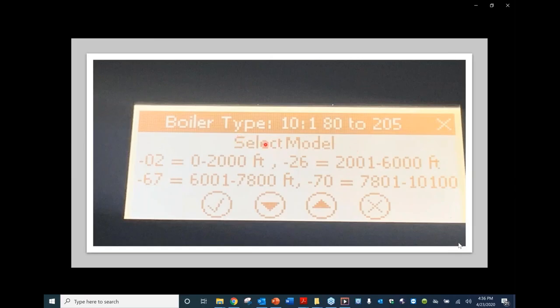We will select the model through the arrows, but this is going to give us the outline for our altitude. Sea level is 0 to 2,000 feet. 2,001 to 6,000 feet would be 26. 6,7 will be 6,001 to 7,800 feet. 7,801 to 10,100 would be all of our altitude settings. We would press the up and down arrows to scroll through the boiler make and model.